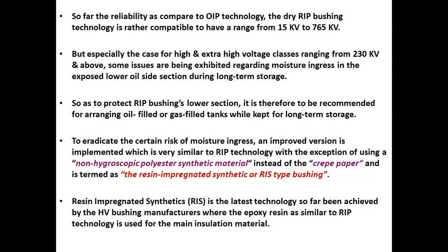To eradicate the risk of moisture ingress, an improved version was implemented which is very similar to RIP technology, with the exception of using a non-hygroscopic polyester synthetic material instead of crepe paper, and is termed the resin impregnated synthetic, or RIS type bushing. That is, resin impregnated synthetic. Resin impregnated synthetics is the latest technology achieved so far by the HV bushing manufacturers, where epoxy resin, similar to RIP technology, is used for the main insulation material.